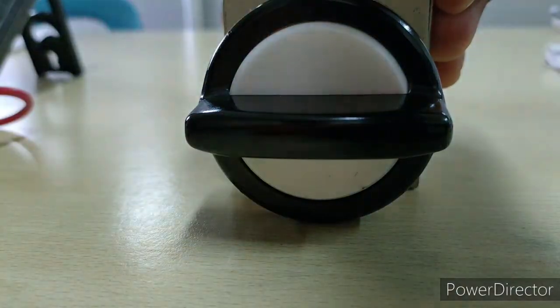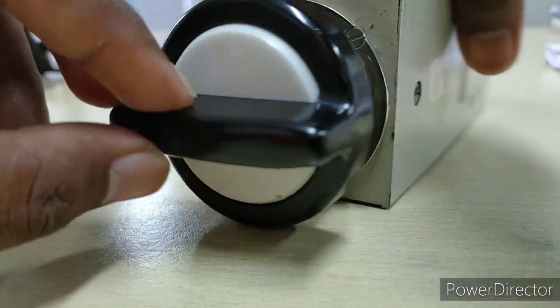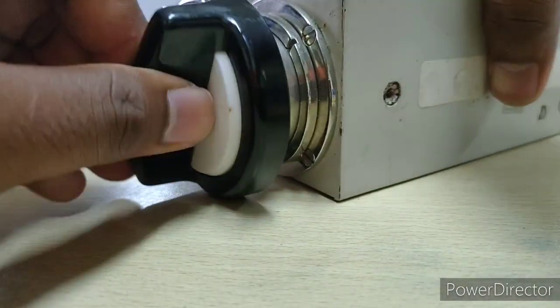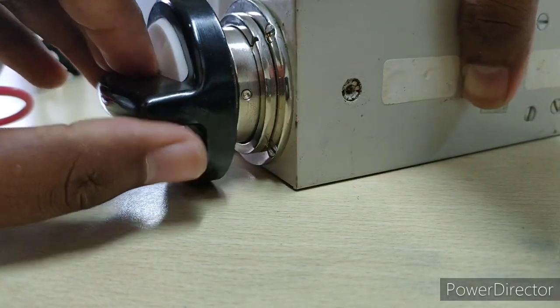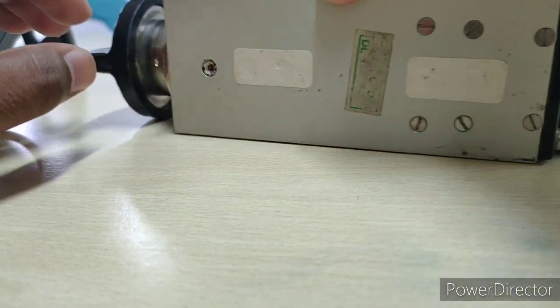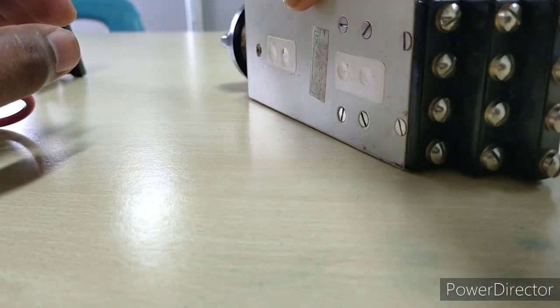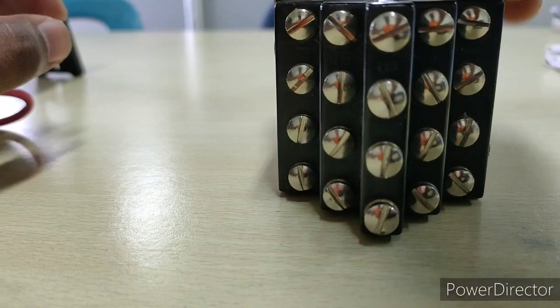This is the off position of the breaker. If the breaker is on and I put the discrepancy control switch in the on position, then the light inside the switch will be blinking and that indicates your position is wrong. That's called the discrepancy.